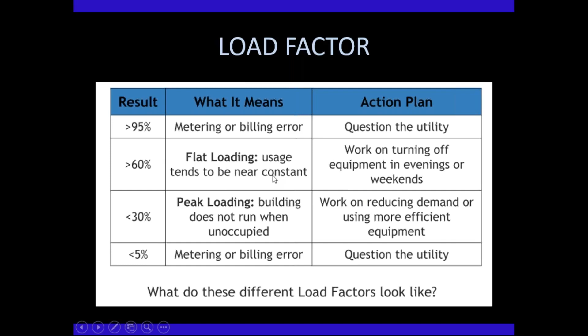A load factor of 60% looks like this in general: on weekends or off hours, half the power is running, and most of the building or part of it is open. On weekdays they use a lot, then turn off half the building during off hours. This looks like a hospital to me. Hospitals should have load factors around 60%, maybe 50 or 70, but generally around 60.